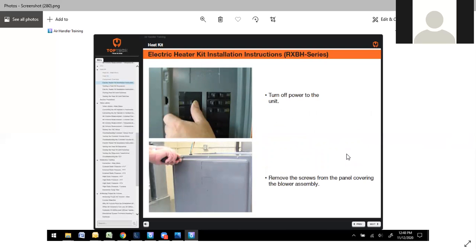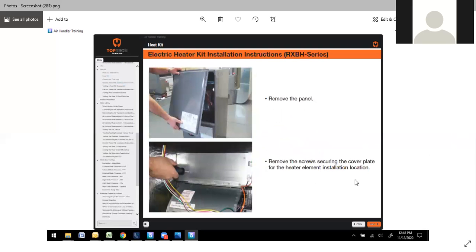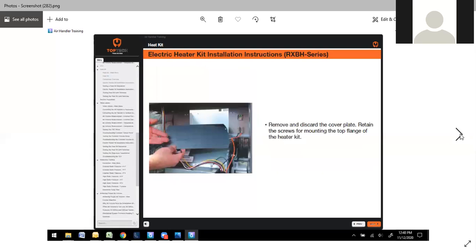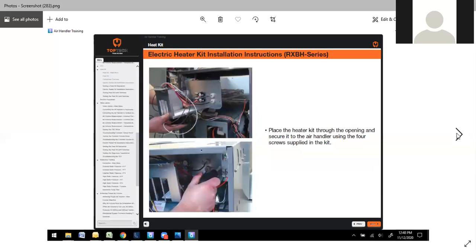To install one of the kits, they've actually made it pretty simple. Normally, you're not going to be hooked up yet, but you could be hooked up if you're replacing one. Turn the power off to the unit. Remove the screws that hold the electrical panel on. If it's a brand new unit, you're going to have this blank off plate right here. Remove that blank off plate. At that point, you can place the heater kit through the opening. Once you get it in there, it's not terribly difficult. If you line your screws up, it will be in there safe and secure.